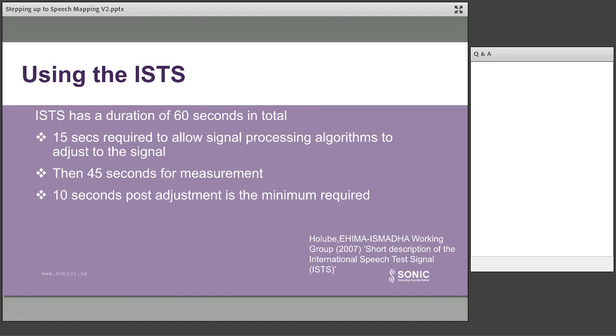So you do need to run that signal for quite a while. You can't just turn it on, get a quick curve and come out again. Otherwise, you haven't really recorded the true LTAS or the average. Now, in your metrics, of course, what you'll find is that that 60 seconds is looped. And so the signal will continue, so that enables you to fine-tune your hearing aid as you go along.